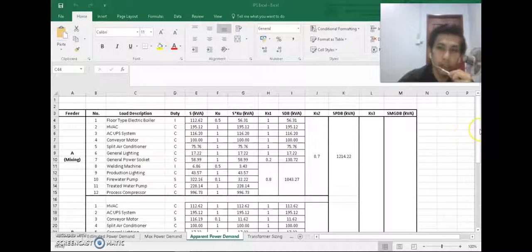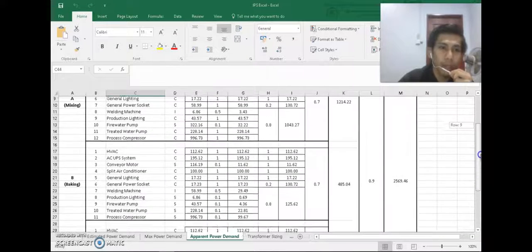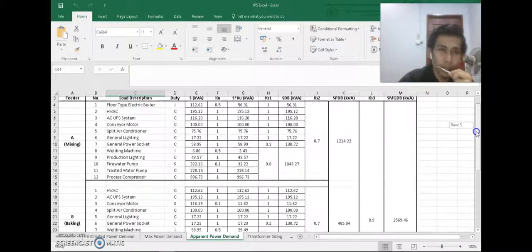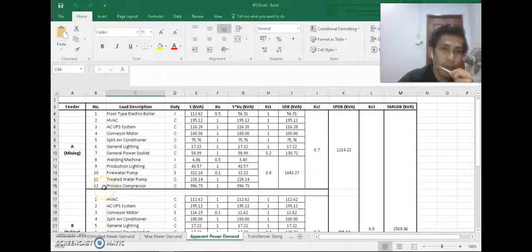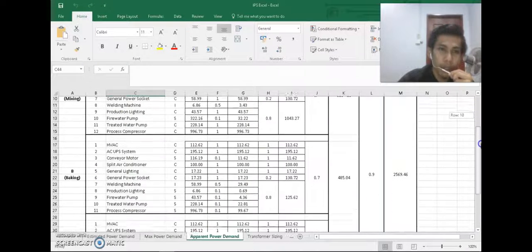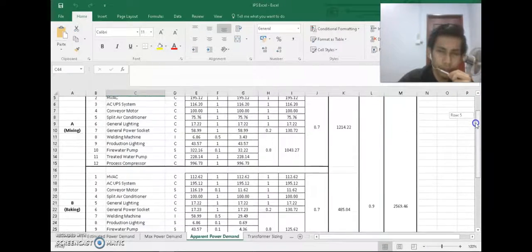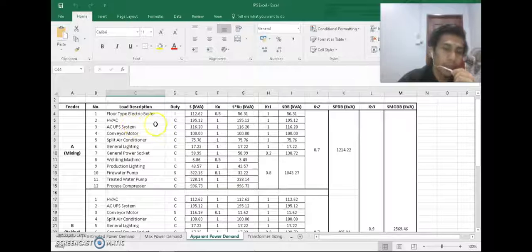So today I will explain a little bit about the Excel, which is the apparent power demands. We have three feeders: feeder A mixing, feeder B baking, and feeder C packaging. For feeder A, we have 12 loads. Feeder B has 11 loads, and feeder C also has 11 loads. We arrange the loads based on the voltage and whether the load uses a motor or not. For example, numbers 1 until 7 do not use a motor, but numbers 8 until 12 use a motor.